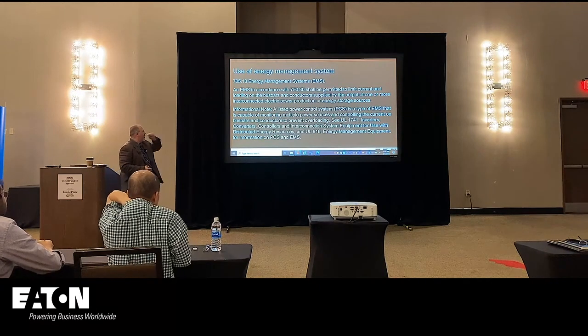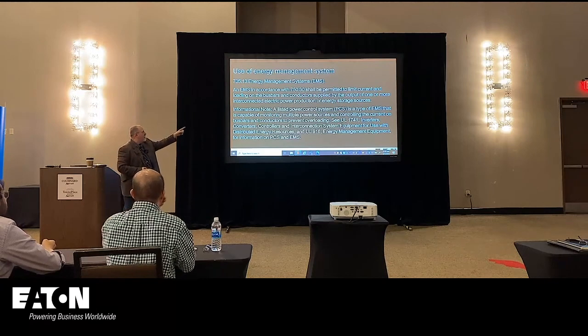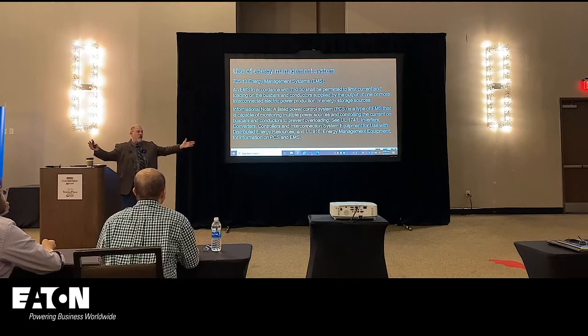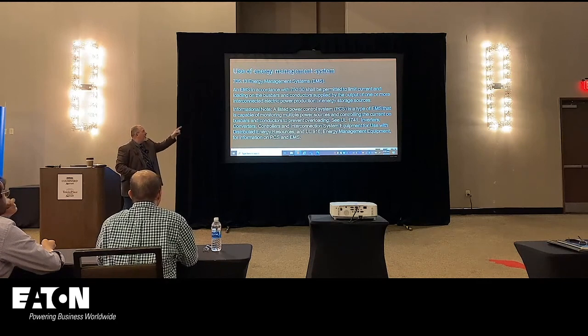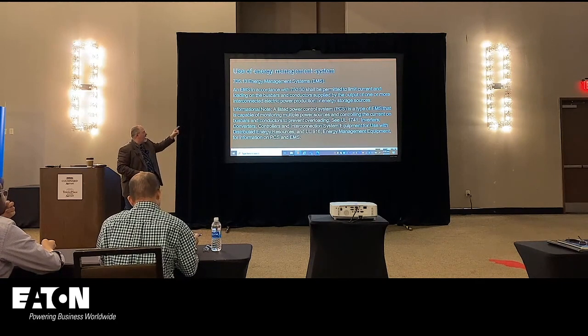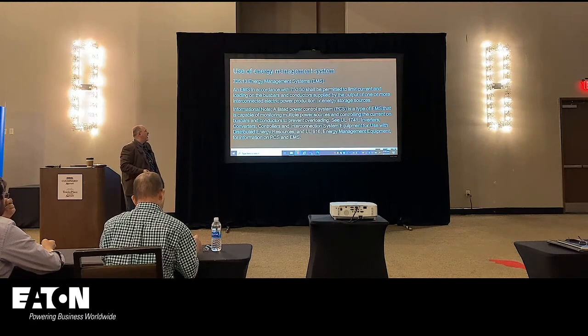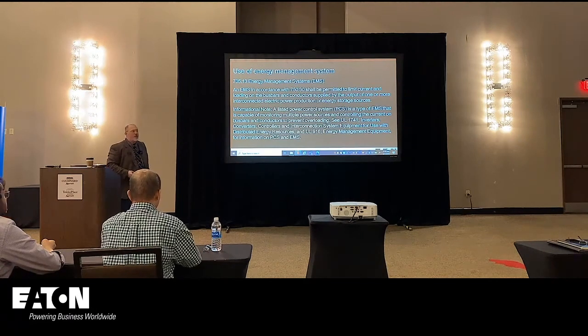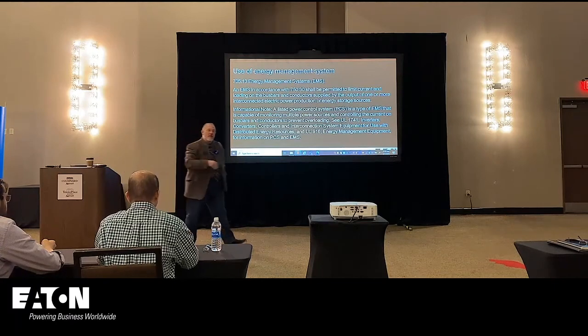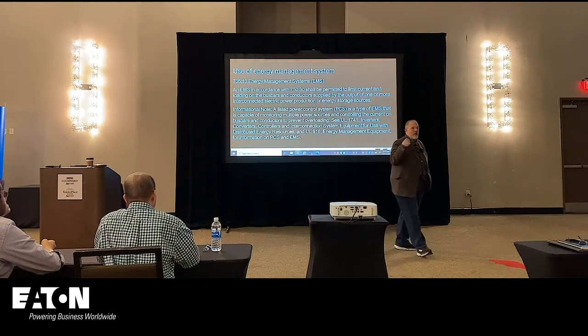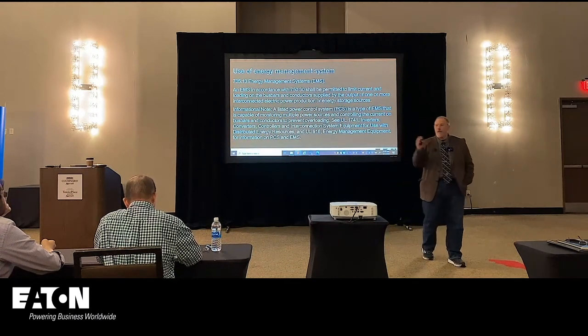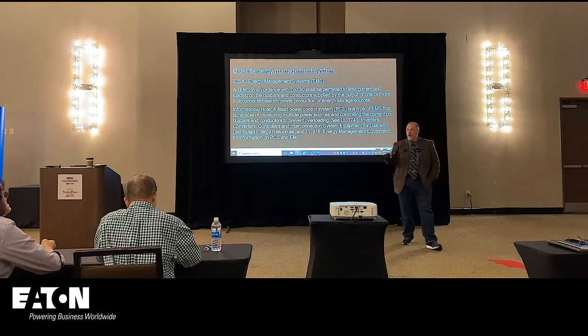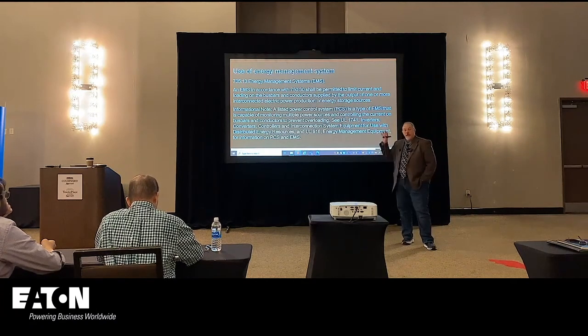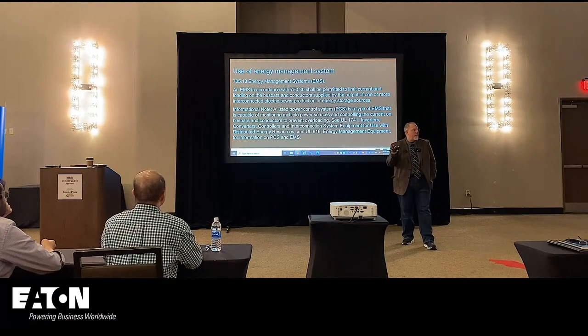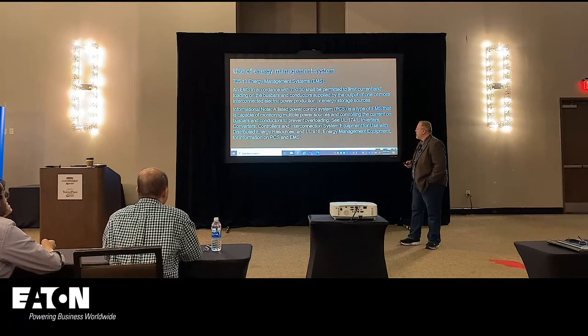There's your 705.13, an energy management system in accordance with 750. 750 is for energy, the title of the whole article is Energy Management Systems, permitted to limit current and loading on the bus bars and conductors supplied by the output of one or more interconnected electric power production or energy storage sources. So we're relying on this system to size our equipment, and it better work. So the standards are addressing this. I think there's probably some opportunity for the UL standards to take a look at the listing requirements around these energy management systems and make sure that they're going to perform the way we need them to perform.